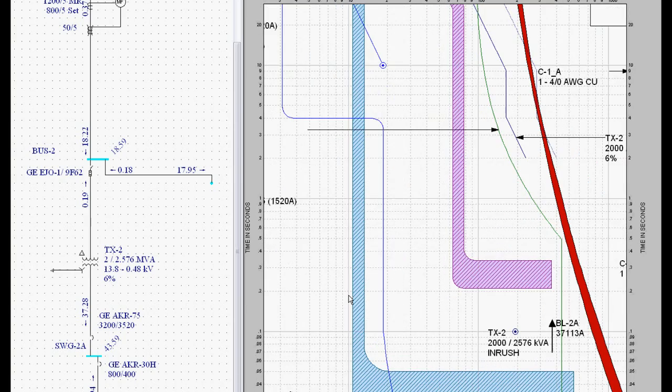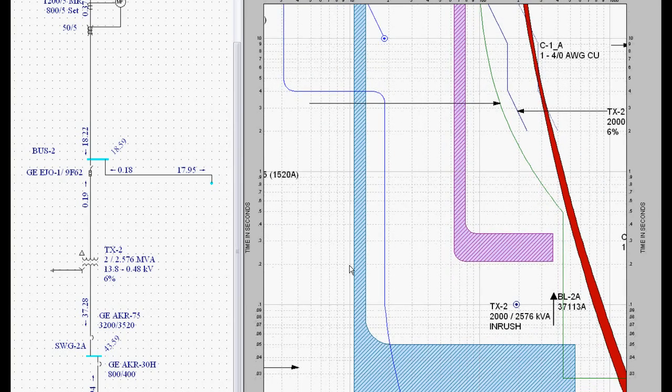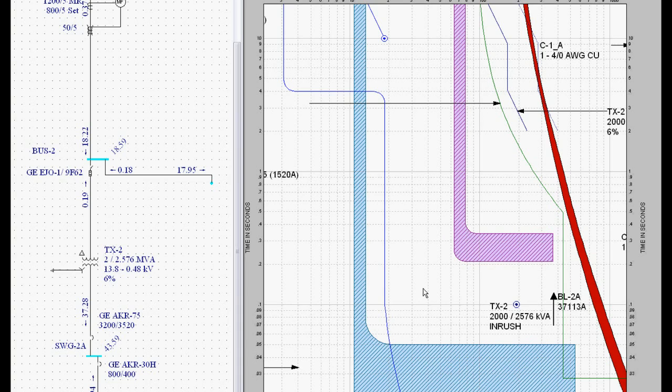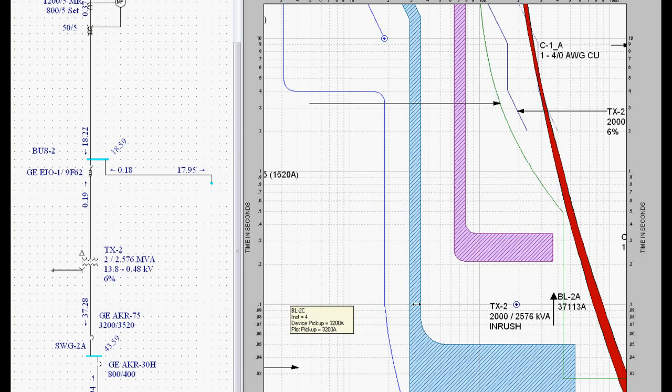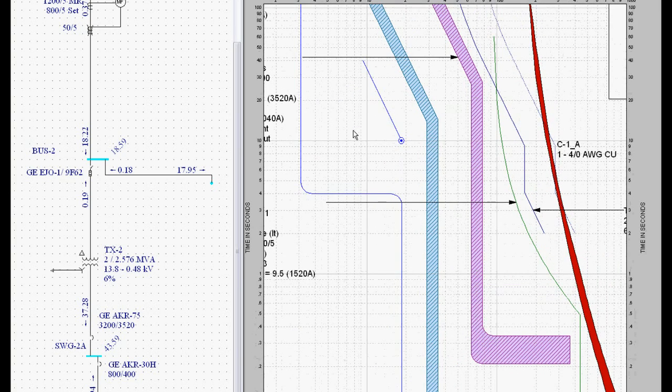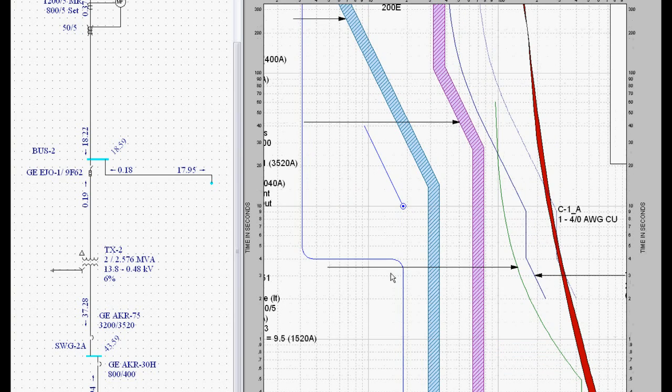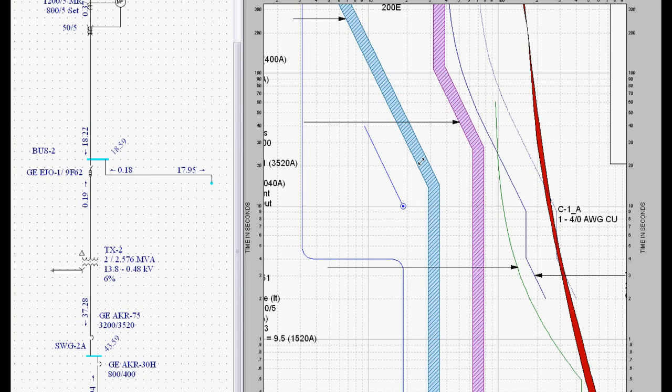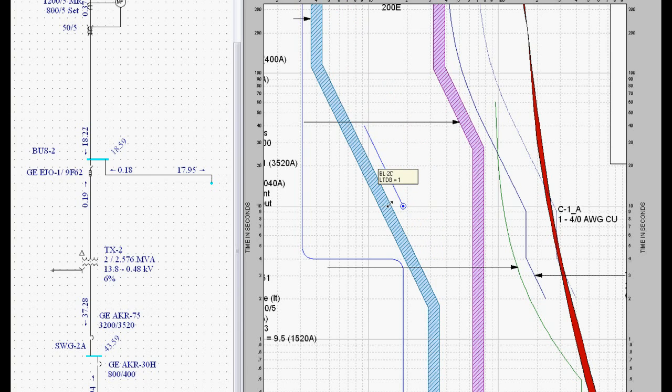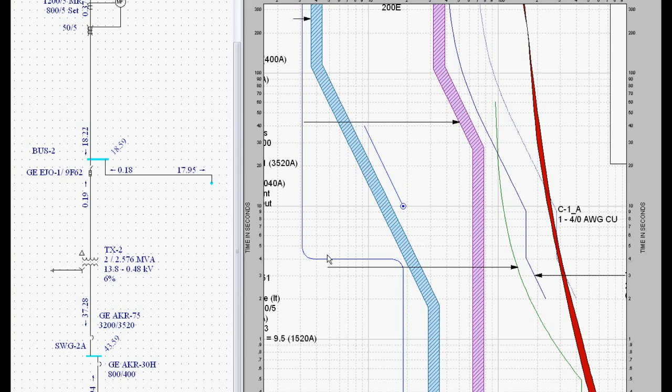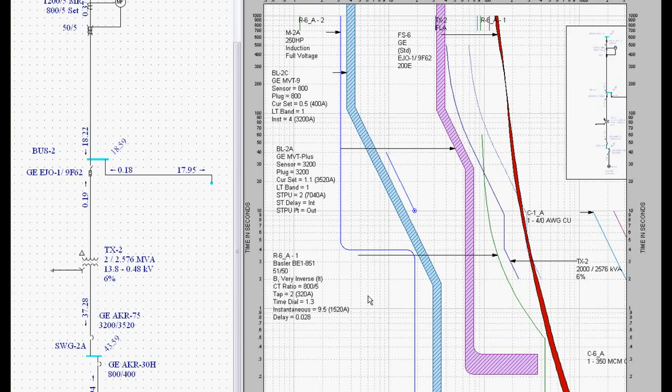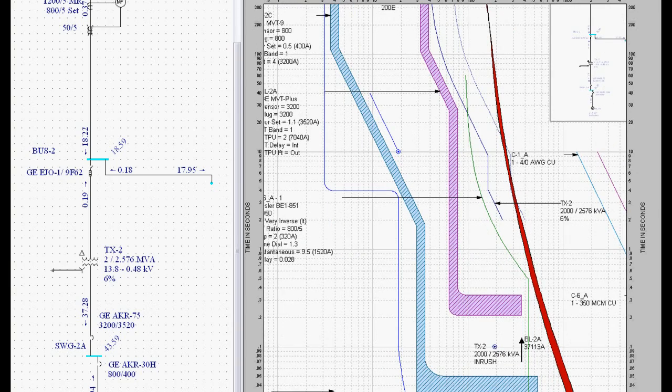Now, we won't get into a course on protective device coordination at this point in time. But you can see if I drag this over to 1.5 that this motor starting curve is going to trip. So I need to set it above these protection boundaries. In this case, if I had a locked rotor jam, my motor stall time is going to burn up here at 10 seconds. And my long time delay band does not protect me until I get it down to a 1.0 demand. And so on. So you can see exactly how we go about this protection.